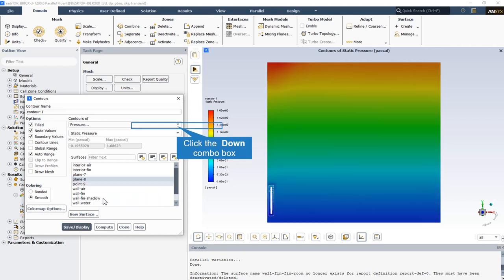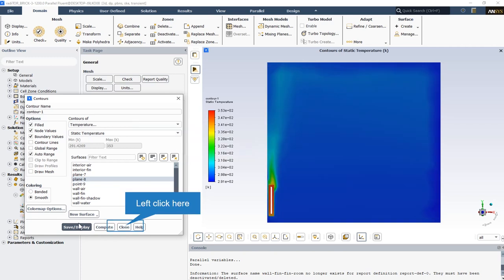The pressure contour. And finally we can display the most important two-dimensional contour of the CFD simulation as the temperature contour. As we can see the minimum temperature magnitude is about 291 in the corner of the room and also the lateral side of the room that are far from the radiator. And also the maximum temperature occurs on the wall fins of the radiator that is equal to the maximum temperature of passing water flow equal to 353 degrees Kelvin.